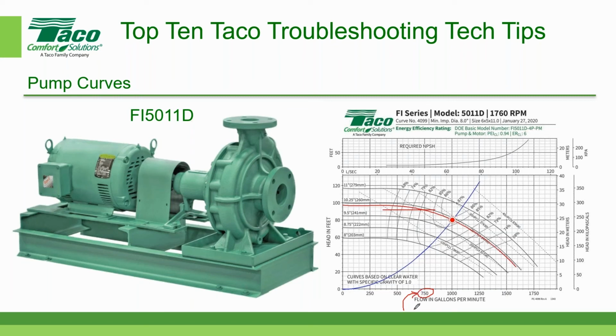Now, what we would prefer is to have the flow measured independently so that we could check it. So again, we would prefer to have the flow either through a calibrated, permanently installed flow meter, or a non-invasive ultrasonic flow meter that's been recently calibrated. Because we really do need to understand what the relationship is between flow and head.